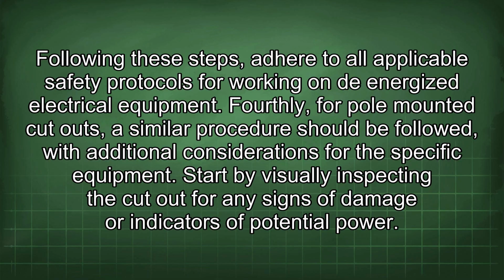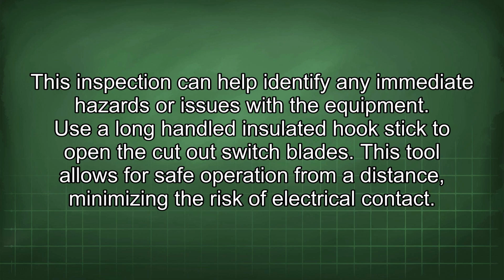Fourthly, for pole-mounted cutouts, a similar procedure should be followed, with additional considerations for the specific equipment. Start by visually inspecting the cutout for any signs of damage or indicators of potential power. This inspection can help identify any immediate hazards or issues with the equipment. Use a long-handled insulated hook stick to open the cutout switch blades. This tool allows for safe operation from a distance, minimizing the risk of electrical contact.